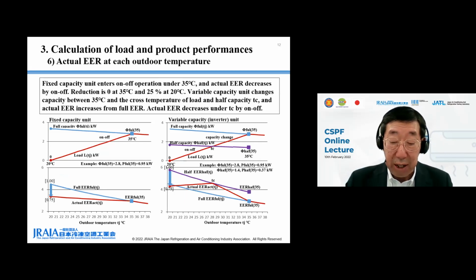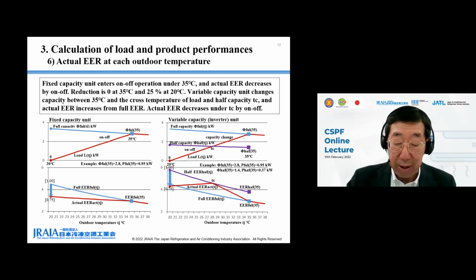This page shows actual EER at each outdoor temperature for fixed and variable capacity unit. The upper left figure shows load and full capacity, and the lower left figure shows full and actual EER for fixed capacity unit at each outdoor temperature. For fixed capacity unit, load is lower than full capacity under 35 degrees C, and the unit enters on-off operation in this zone. Actual EER decreases from full EER by on-off. Amount of reduction is 0 at 35 degrees C and 25% when load is 0 at 20 degrees C. This 25% is according to the default of degradation coefficient 0.25 specified in the ISO standard.